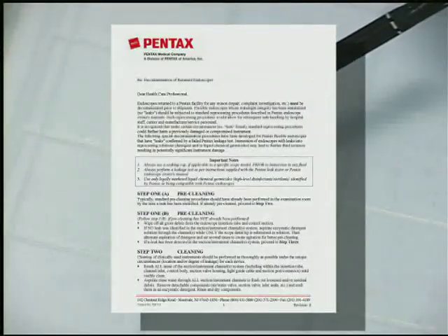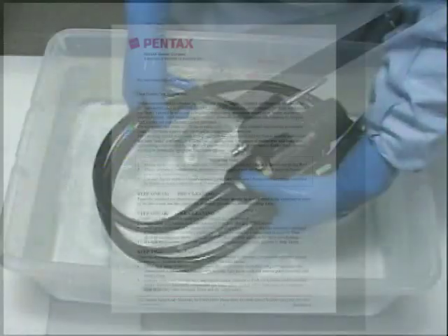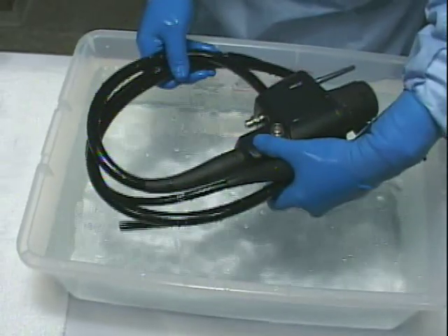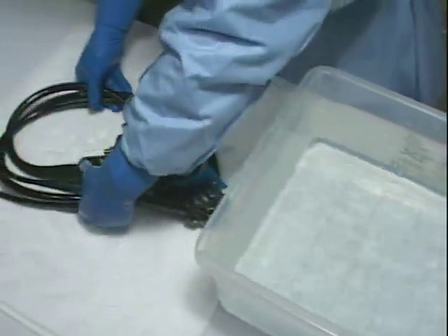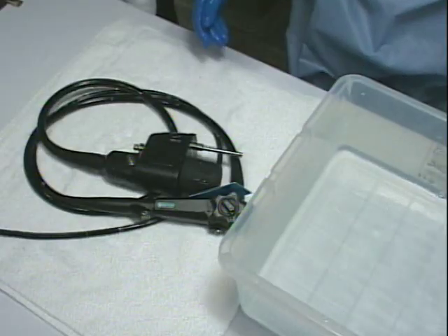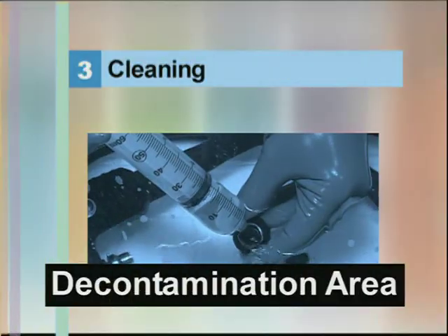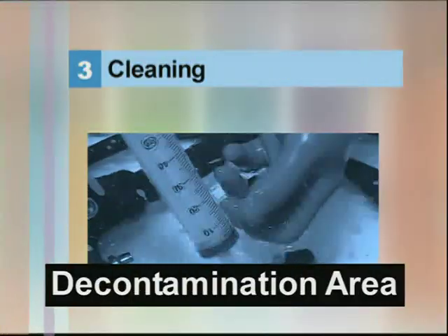If a leak was discovered in Step 2, follow decontamination procedures for returned instruments as described in a separate document and contact your Pentax service center. If no leak was discovered in Step 2, you may proceed with standard cleaning and disinfection of the scope. Cleaning in the decontamination area.